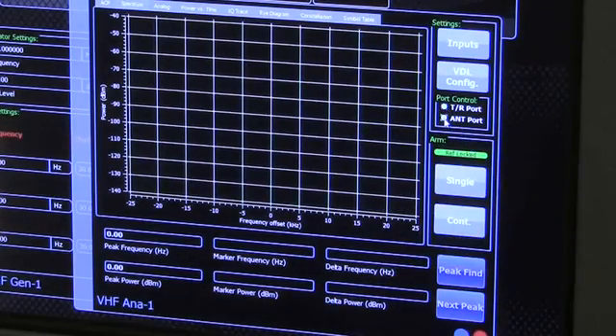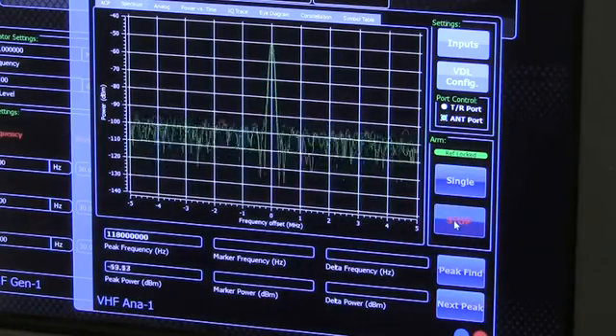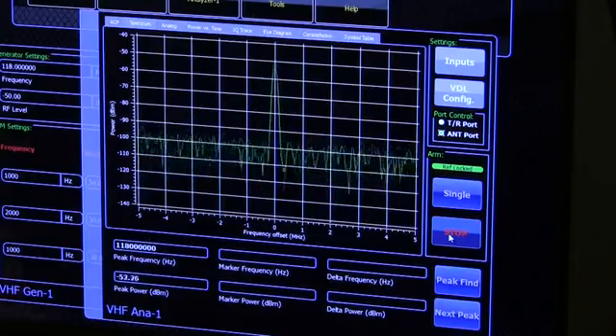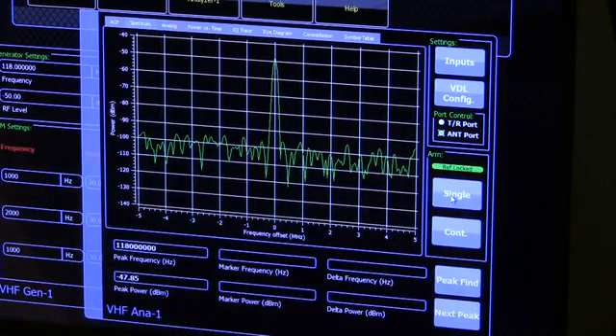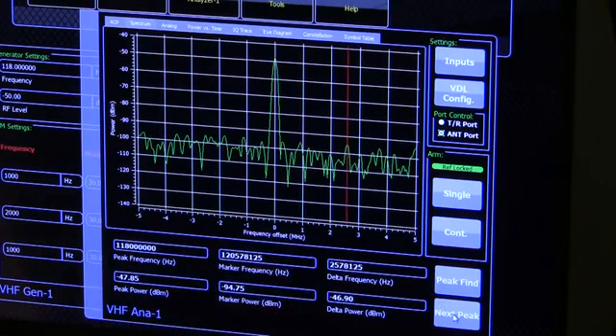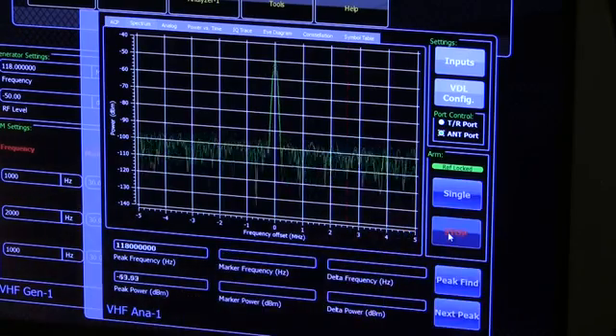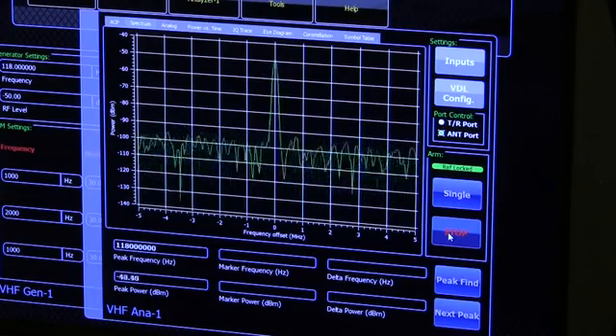Select the antenna port in the Port Control section. Start the sweep by touching the continuous button in the arm section. To use the marker functions, touch stop, then the single button in the arm section. Touch Peak Find and observe the measurements. Touch continuous in the arm section again. Note that the signal is jumping a bit — this is caused by the 2000 Hz modulation signal we have applied to the RF output.